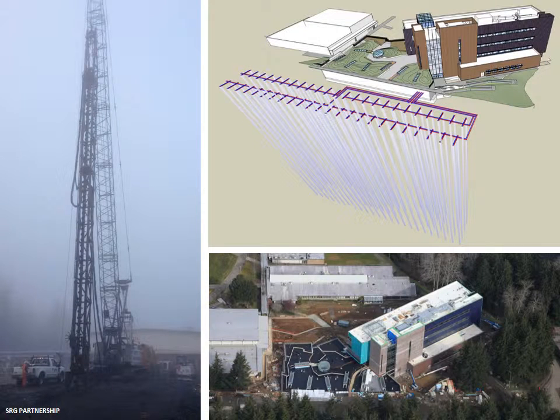Ground source heat pumps provide heating and cooling water to conditioned areas in the building, limiting the use of chiller and boiler equipment. A field of ground-coupled wells were drilled under the adjacent south parking area, and they provide a majority of the mechanical heating and cooling energy by using minimal pump energy to circulate a fluid medium that exchanges its energy with the earth.